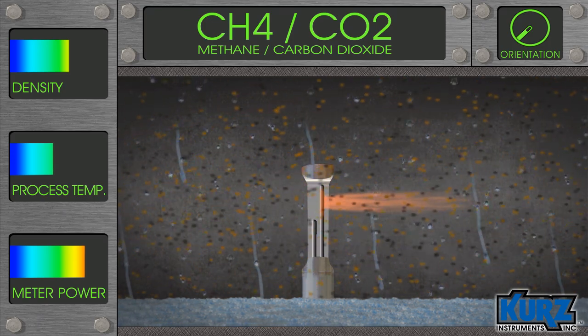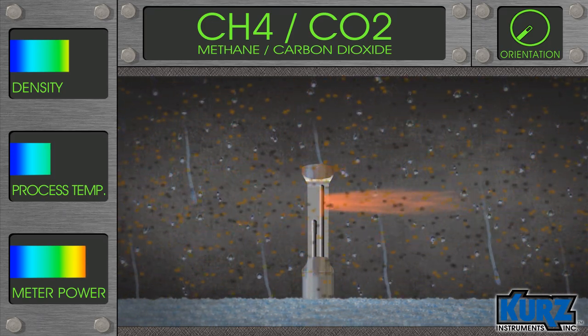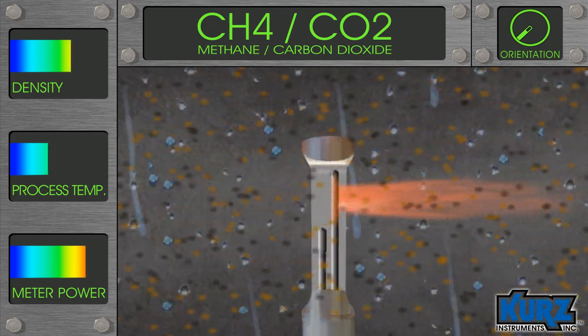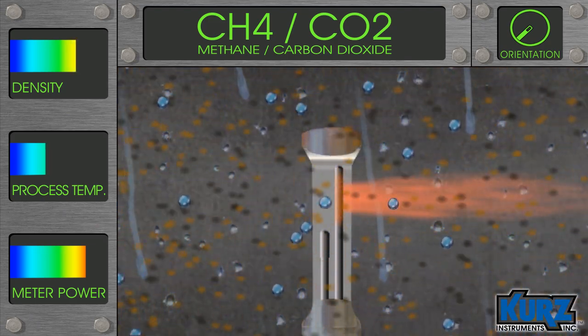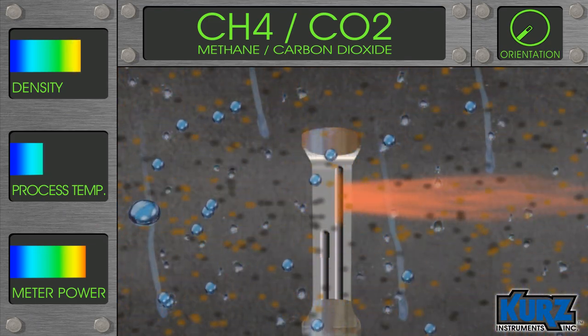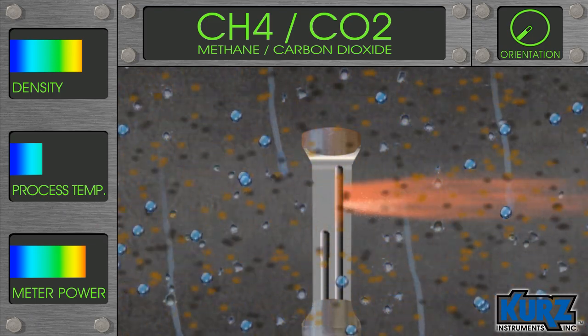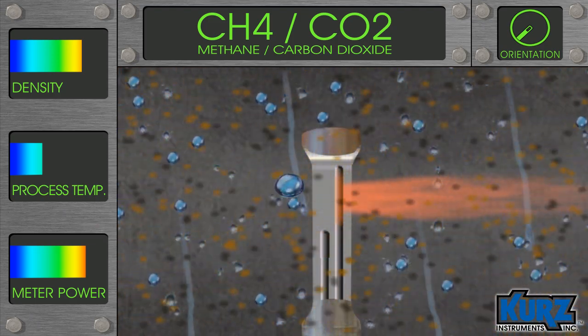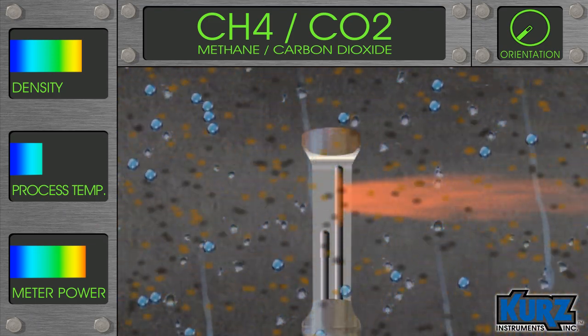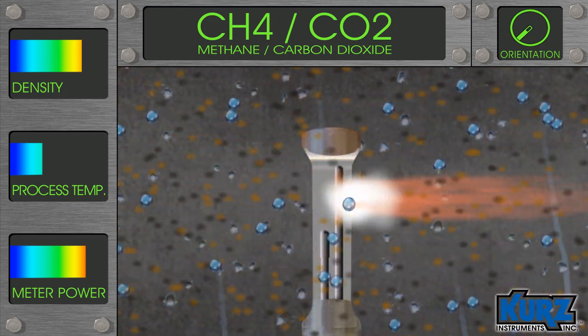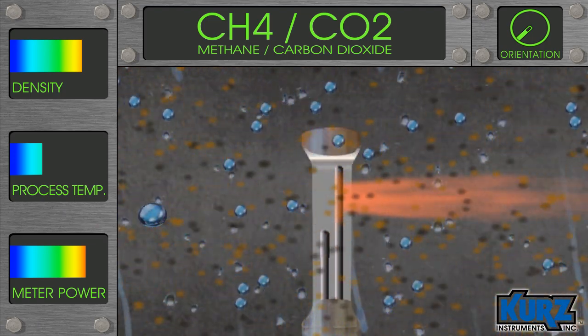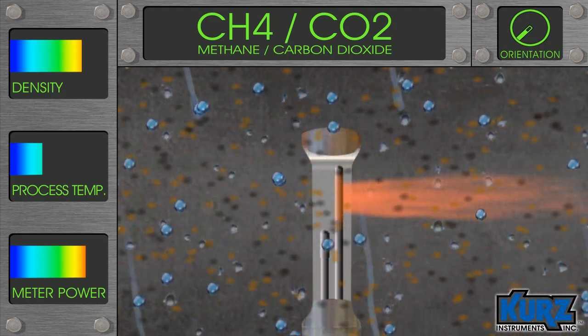The Kurz WGF is the solution for monitoring wet gas flows. The heated sensor operates at 300 degrees Celsius above the process temperature, instantly vaporizing any water on contact. With this superheated sensor, the vaporization energy becomes a small portion of the available signal, so the flow reading is relatively unaffected by the water.